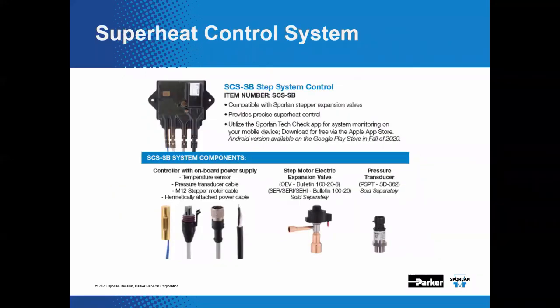Now, Sporlan has recently launched a new standalone control option. Now, this is a fancy one. It's the Superheat control system, or the SCSSB step system control. It's an electronic superheat controller solution that is designed for refrigeration applications using the stepper type expansion valve, or EEV. It is designed to be mounted within the refrigerated space for ease of installation on existing equipment. The controller includes a coil outlet temperature sensor and connectors for the stepper valve, pressure sensors, and electrical power. Because this is an EEV, it needs electrical power. And guess what? I guess the B in the nomenclature here means it's Bluetooth compatible.